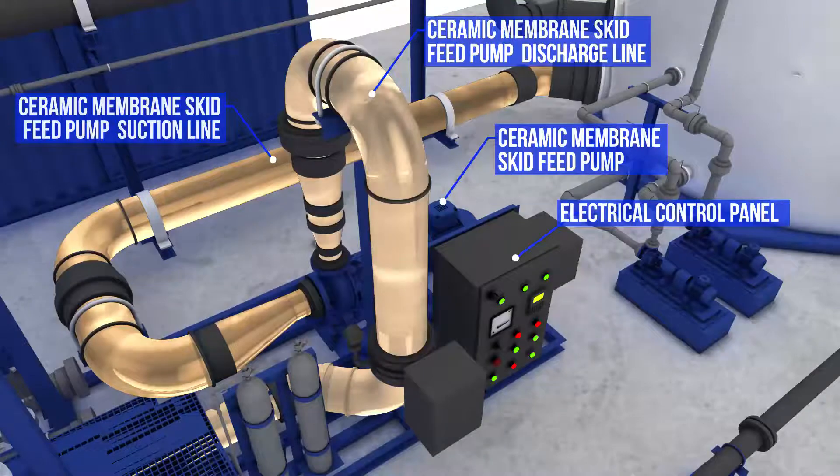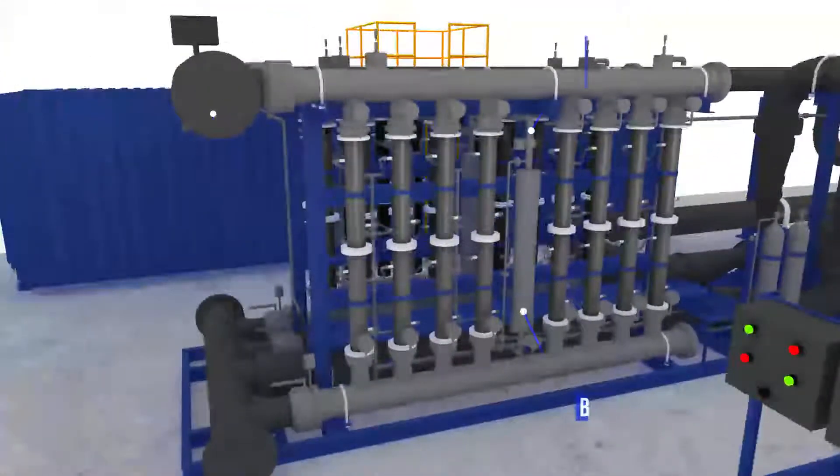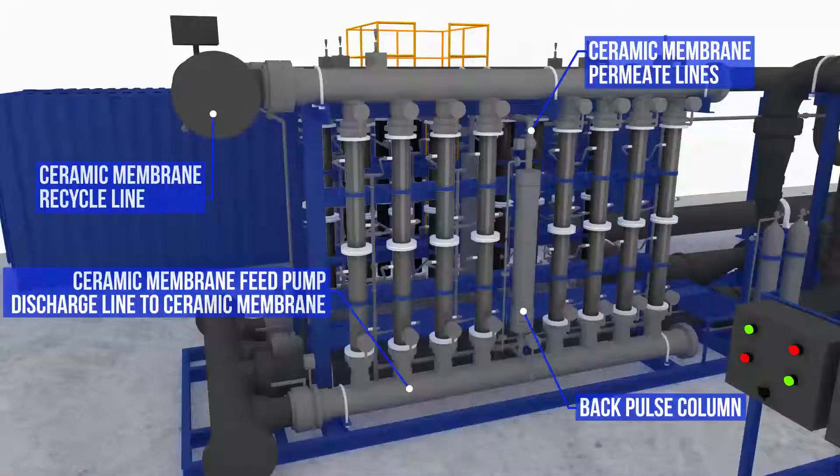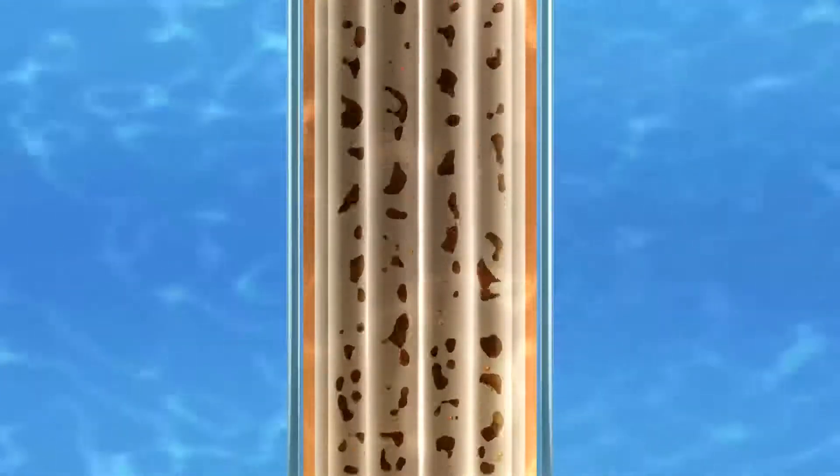The untreated wastewater, known as mixed liquor, is pumped from the anaerobic reactor to the ultrafiltration membrane skid through a feed pump. A tubular ceramic membrane called Cera-Q is used here due to its extraordinary tolerance to chemical, thermal, and mechanical stress.